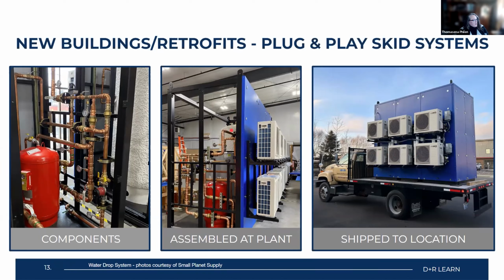You have your storage tank, you've got your temperature maintenance tank, and you've got all your piping right there, all built into the skid. It can get shipped to the site and then craned to the roof or to the ground somewhere near the building, wherever it's going to be served. And you can have your heat pump water heating basically plug and play. And so manufacturers and developers and design engineers are putting these together in a variety of sizes and capacities and shapes based on the load shape of the building, the use, and the design temperature of the location and the climate. And so these guys get shipped. They get craned up to where they need to be. They get connected to the building. They get connected to the electrical and then the controls, and then the system is commissioned.